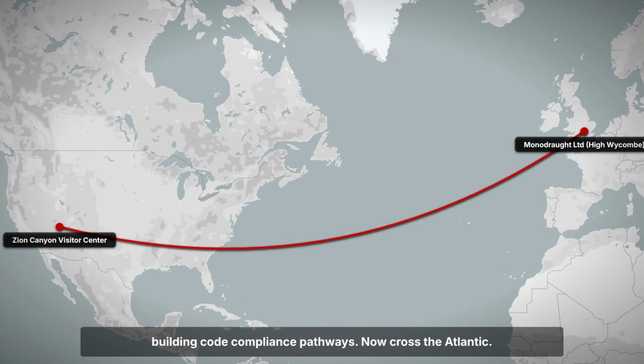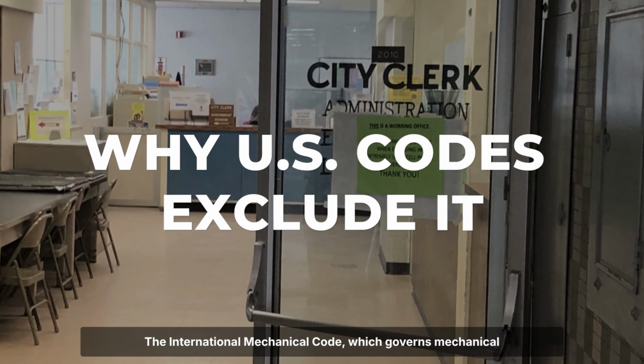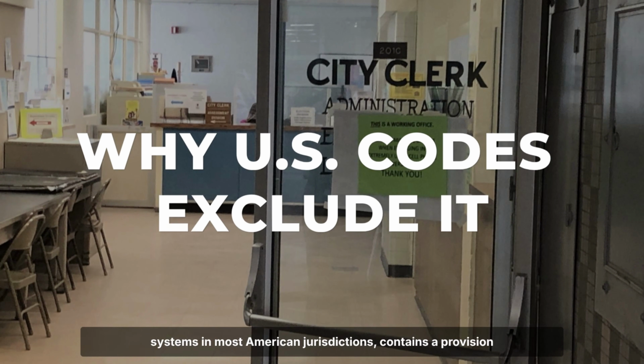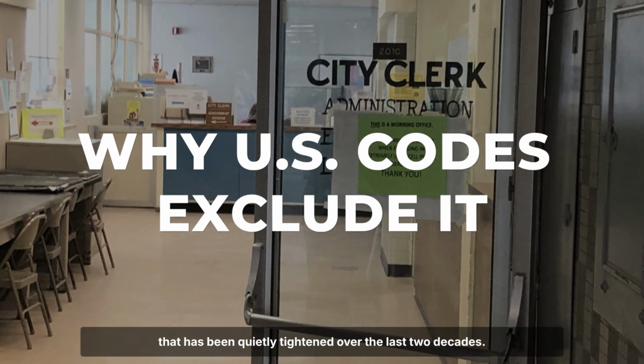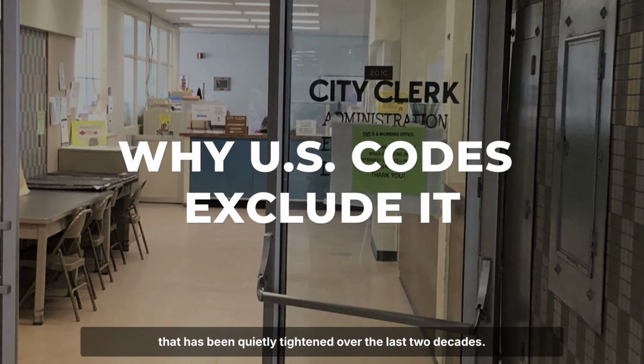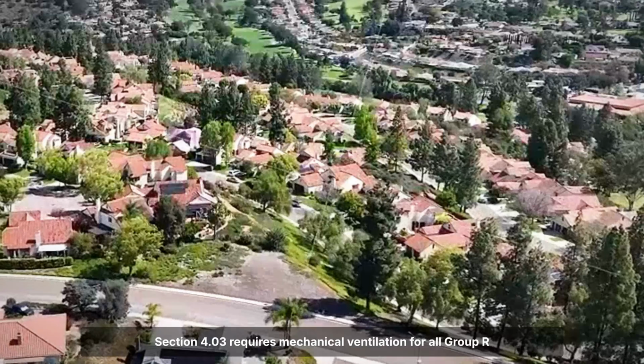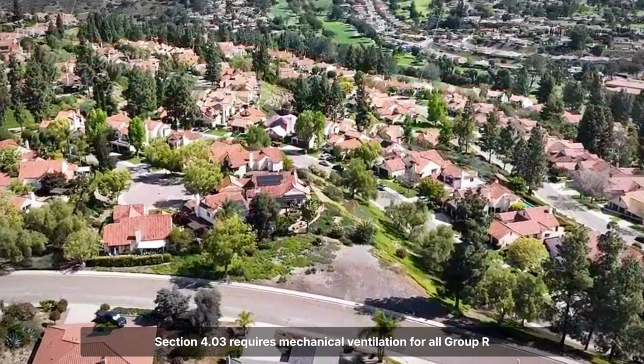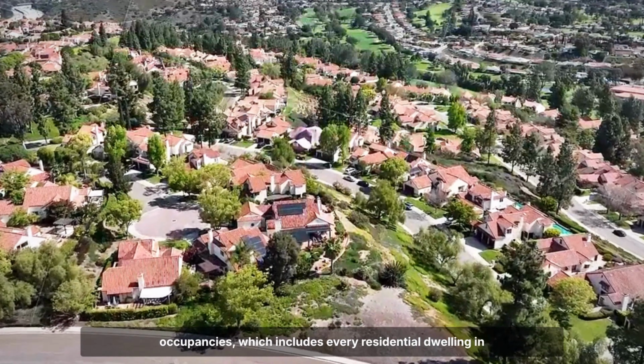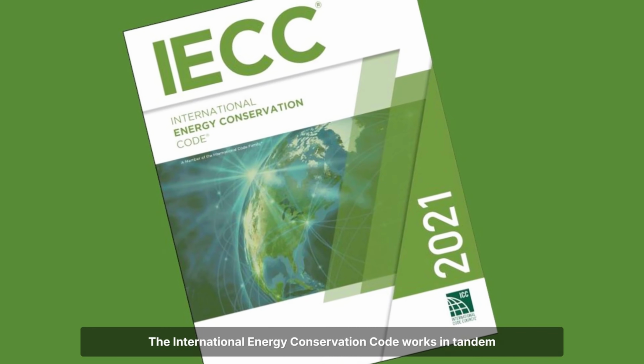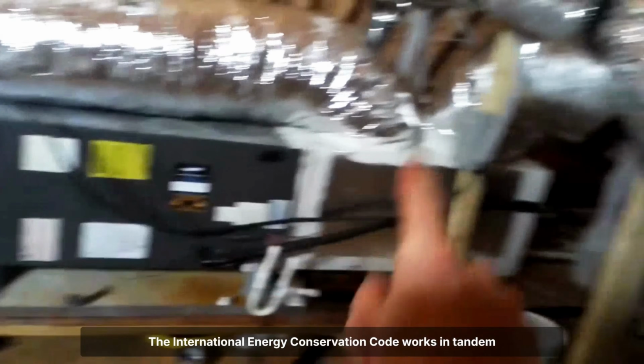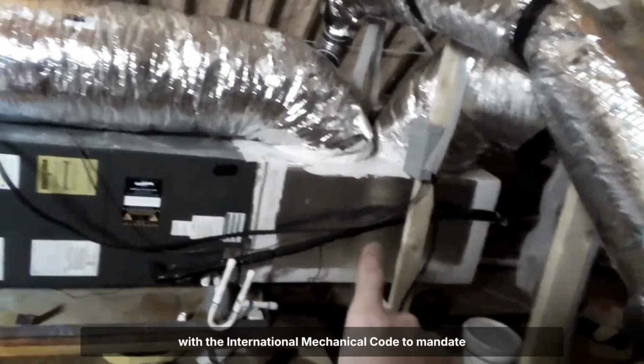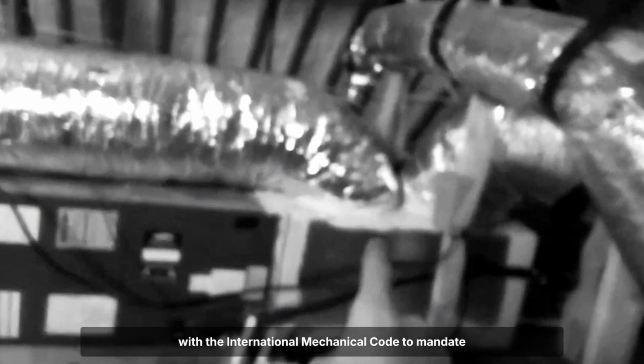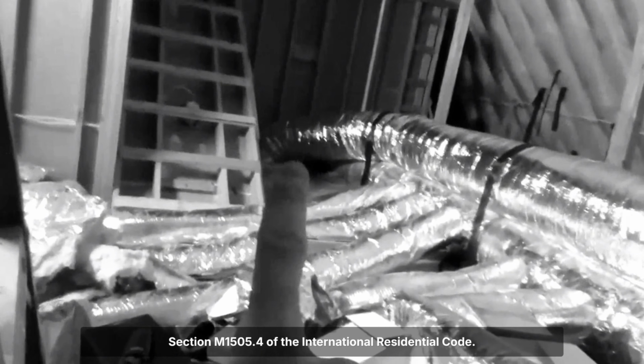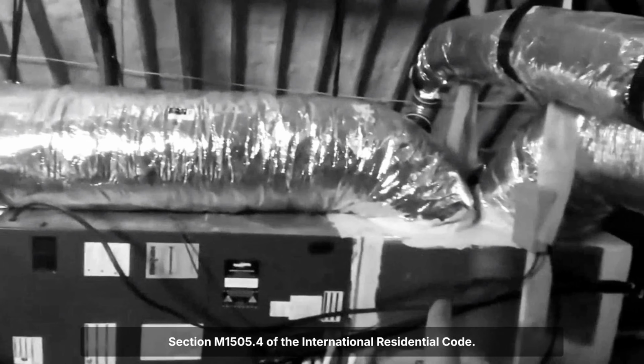Now cross the Atlantic. The International Mechanical Code, which governs mechanical systems in most American jurisdictions, contains a provision that has been quietly tightened over the last two decades. Section 4.03 requires mechanical ventilation for all Group R occupancies, which includes every residential dwelling in the country. The International Energy Conservation Code works in tandem with the International Mechanical Code to mandate whole house mechanical ventilation in accordance with Section M1505.4 of the International Residential Code.